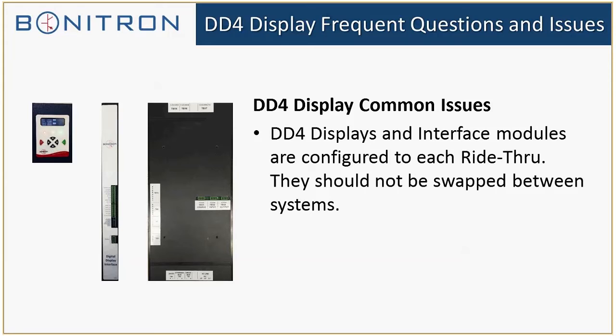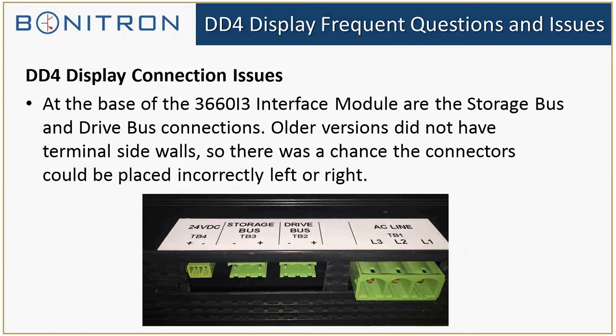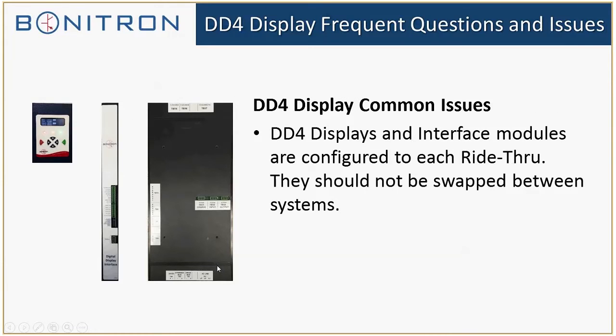The other issue that we've seen with the display modules actually is because of the interface module. Here at the bottom, let me go back to the other slide. Here, this is the bottom of it, and basically you have the 24 volts power coming into here, the storage bus connections coming into here, the drive bus connections coming into here, and then the AC line voltage, which basically senses what the AC line voltage is doing, whether it's lost a phase or just going through a sag, comes into there.